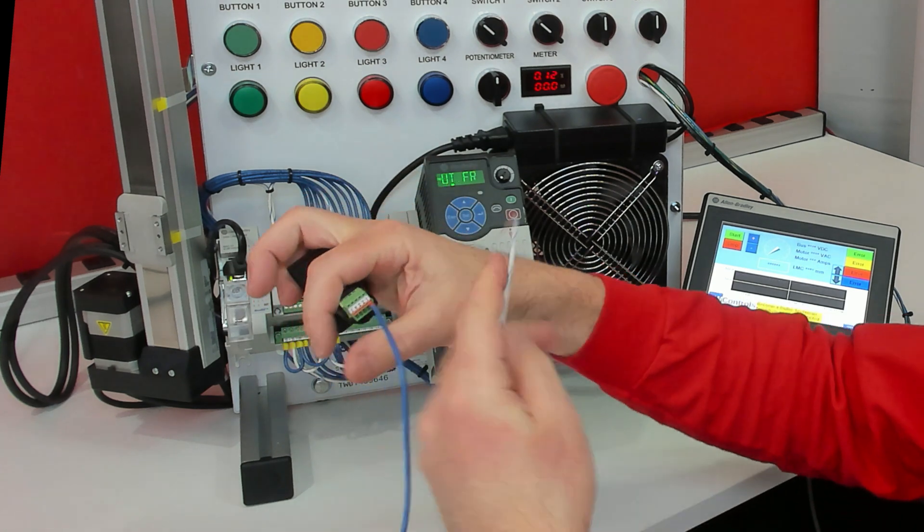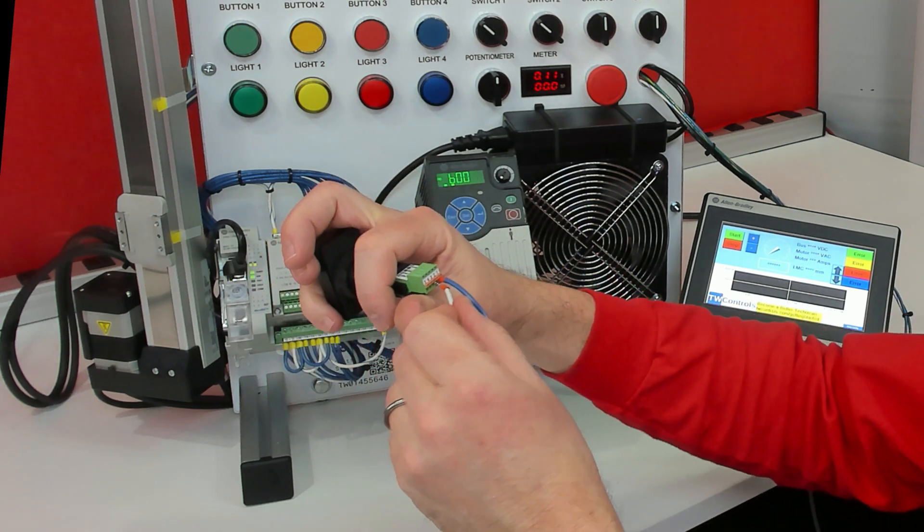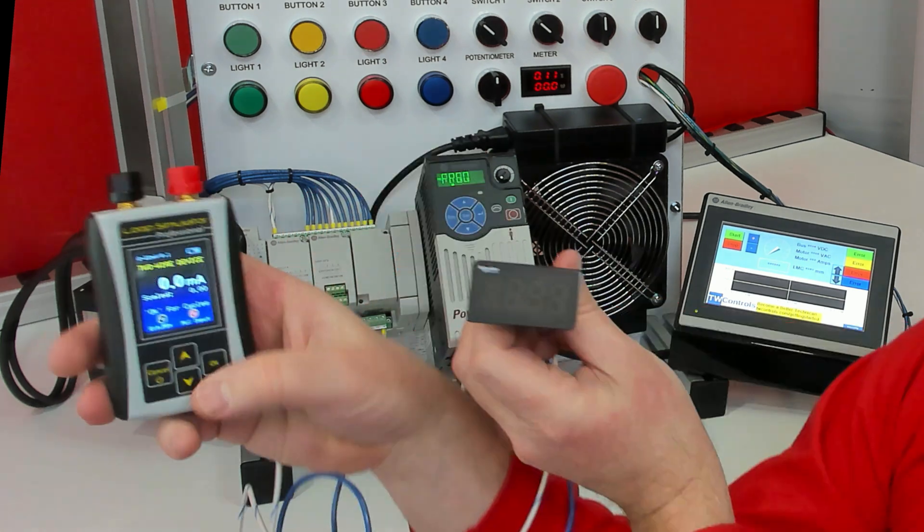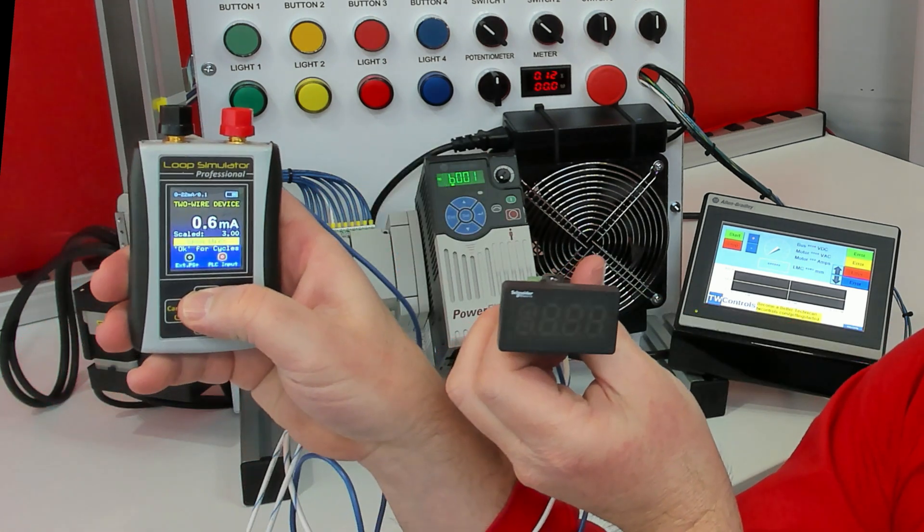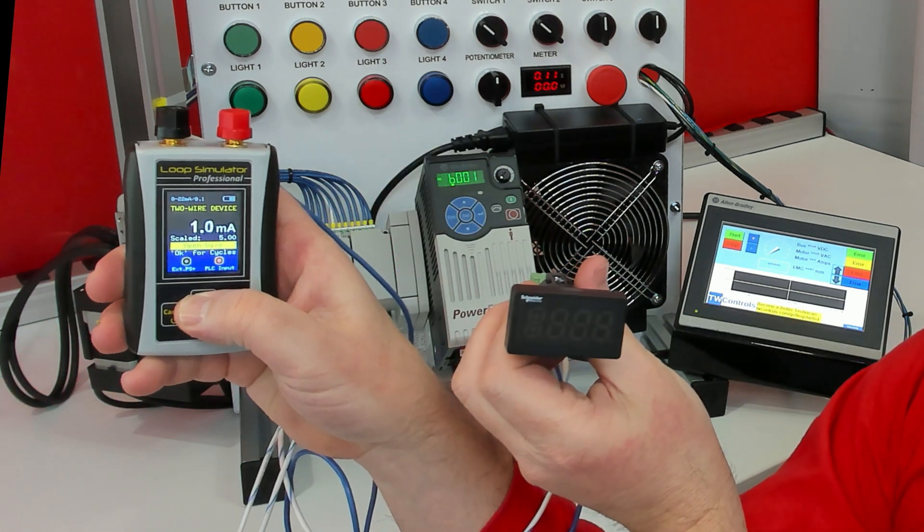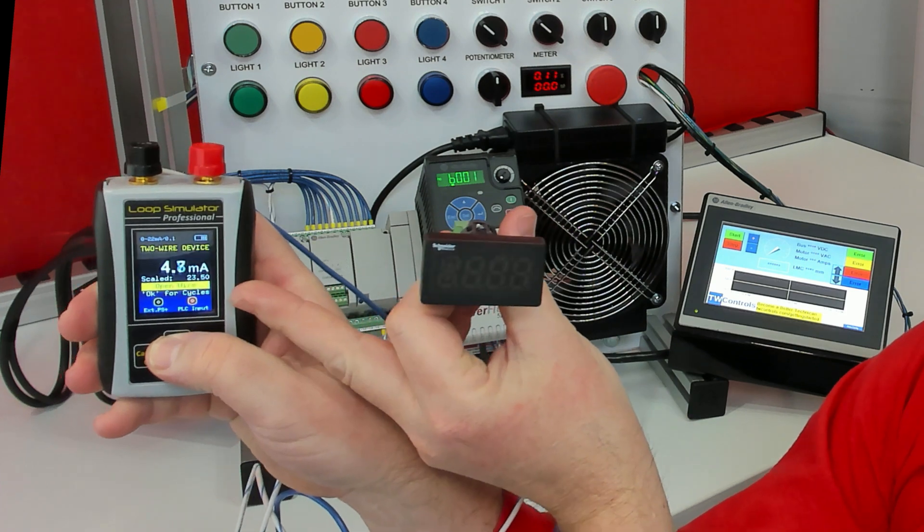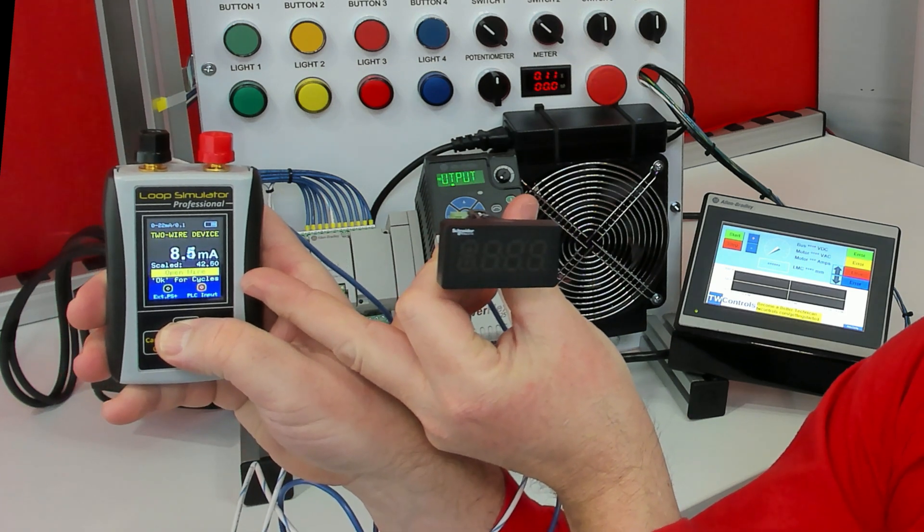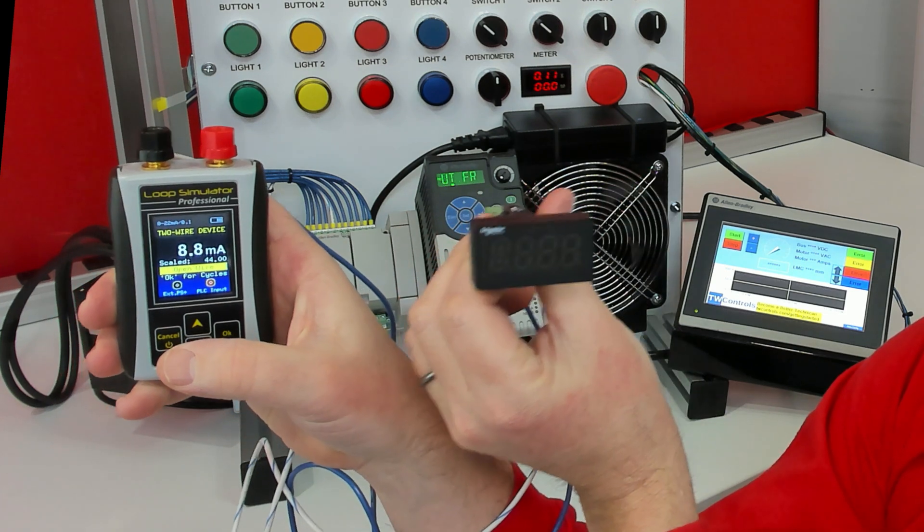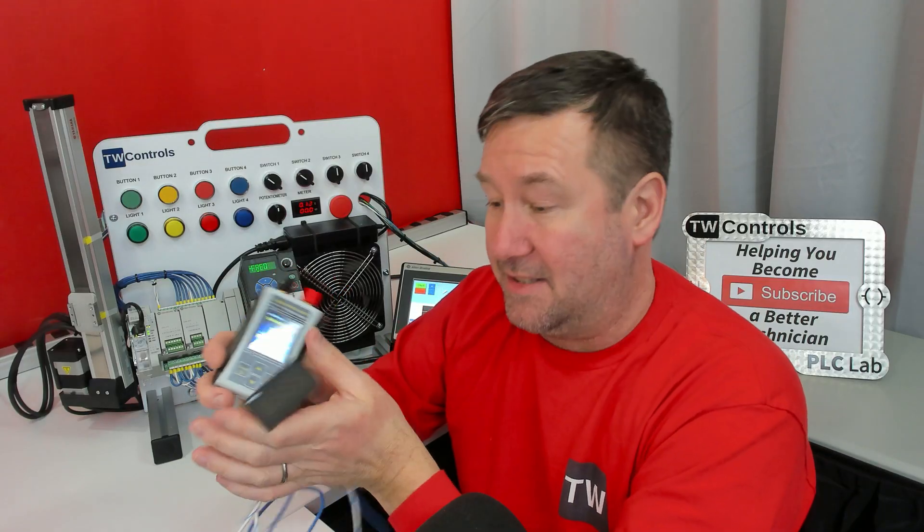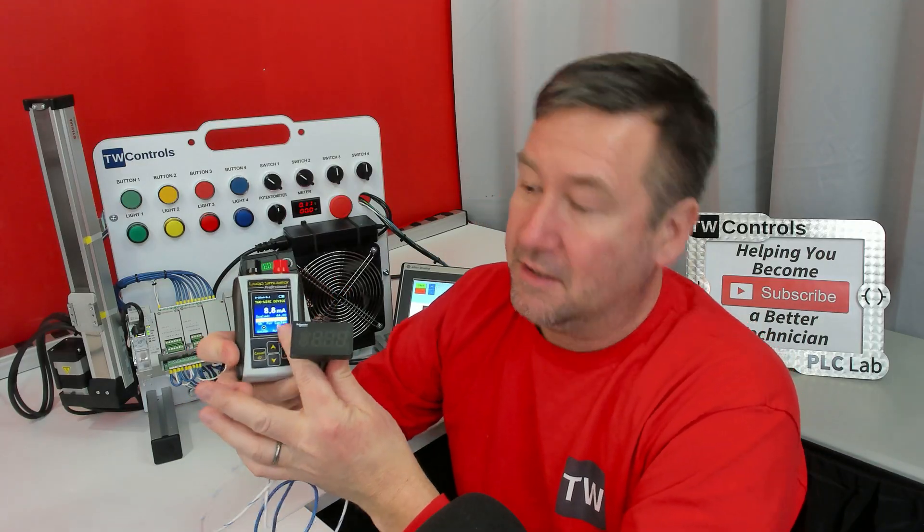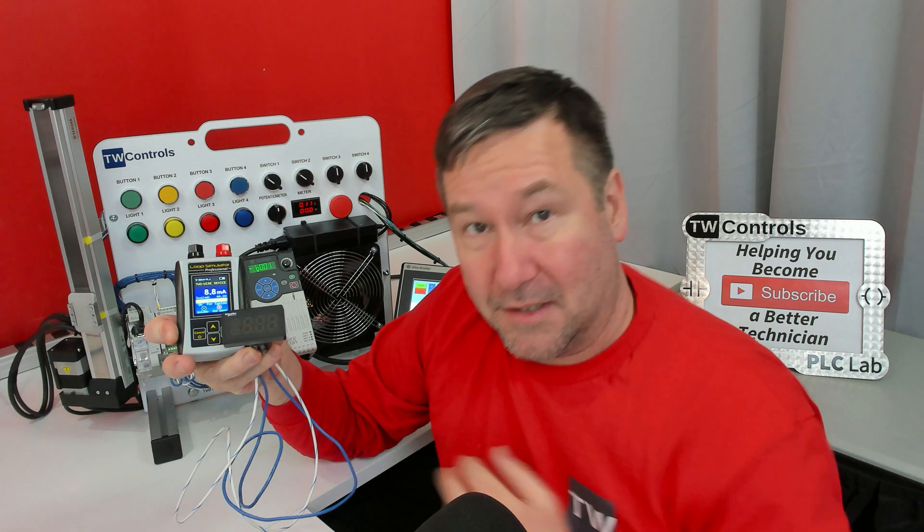And I'll put my white wire into terminal two. And now, if I began bringing my meter up, you see immediately we're getting open wire over here. And we're getting nothing over here. Since this is a current signal, the open wire is mostly determined by can I get current through the circuit.